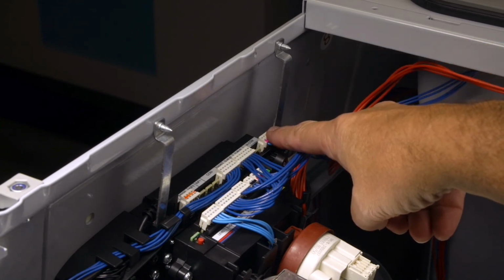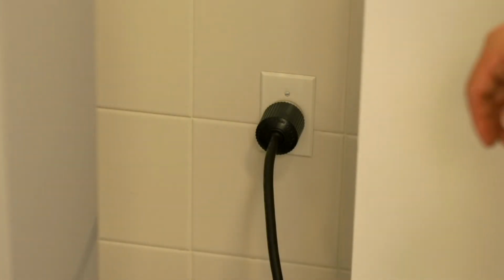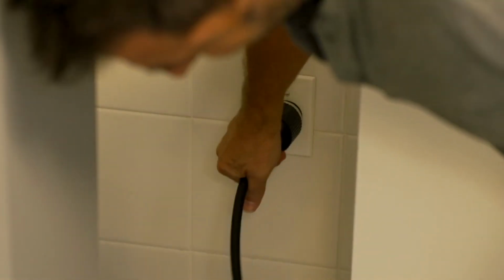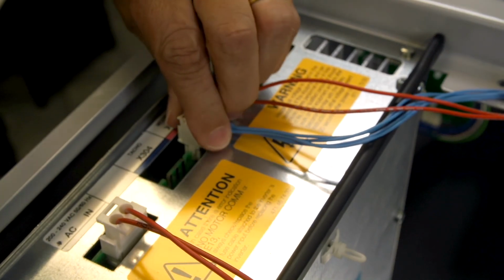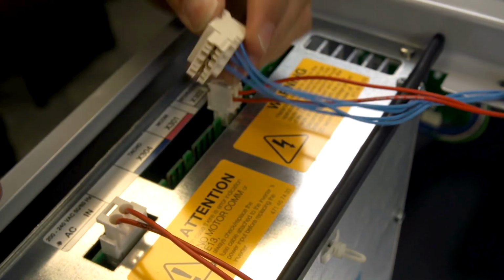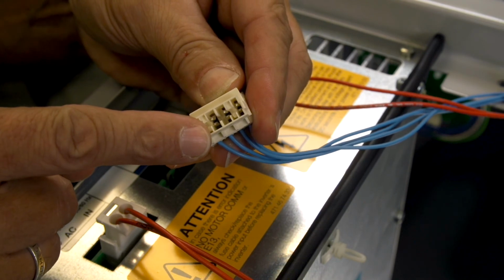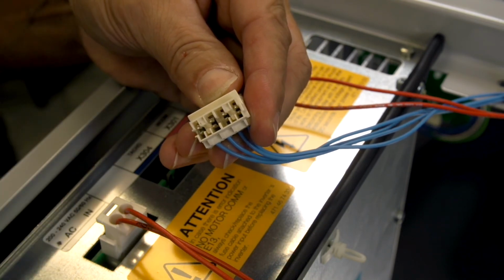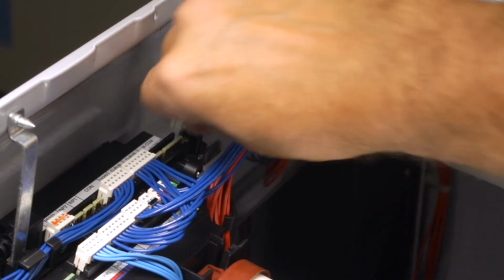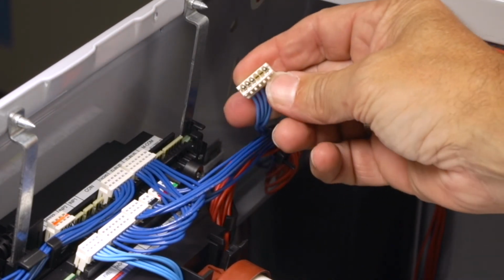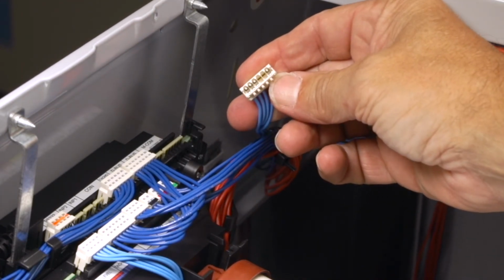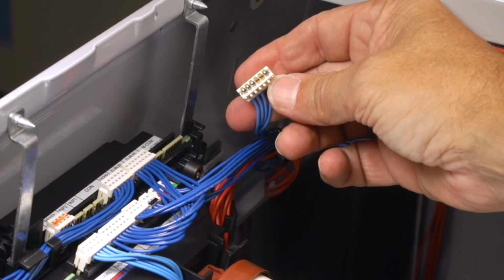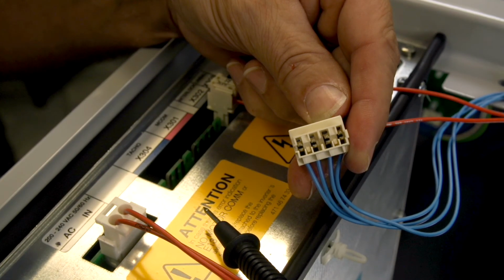As a safety reminder, it is very important that you turn off the power to the machine before moving forward with the following procedure. Now, check each lead of the communications harness between the MCU and the CPU connector for continuity and for short circuits between the leads. First, inspect the connector pins on this harness to ensure that they're making contact with the corresponding contacts on the MCU and CPU circuit boards.